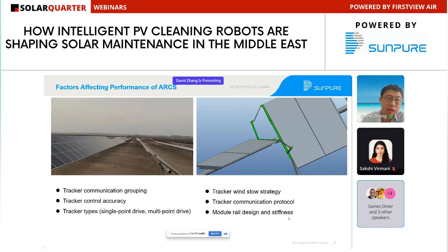This is not difficult to understand, because one robot passes through about 1.5 kilometers in a row, passing through different communication zones of the tracker. Between different communication zones, the synchronization usually isn't very good, so it causes angular differences between adjacent communication groups. As shown in this picture, you can see the very high angle difference between different trackers. This is very common, and also shown here—this is a real site picture.